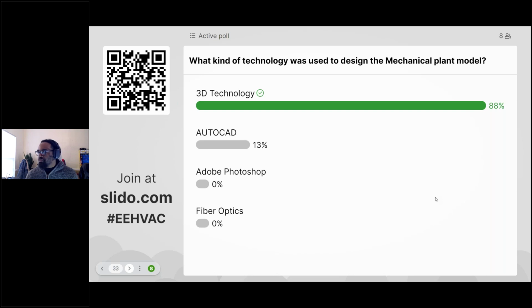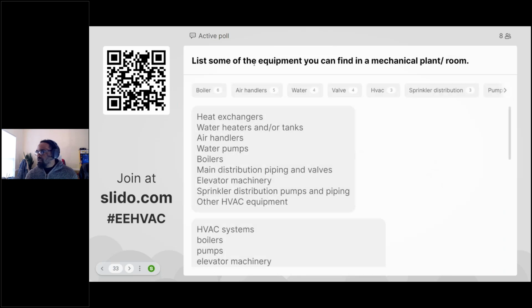Do we have any architects in attendance today? That would be nice to know. List some of the equipment you can find in a mechanical plant or room. And we've got a lot here. We've got boilers, air handlers, sprinkler distribution, HVAC, heat exchangers, water heaters, and/or tanks. Very important to note tanks, for several different reasons, when talking about your hydronic systems, specifically chillers, your air handlers, your water pumps, your boilers, main distribution piping and valves, very important parts of your distribution system. This is where a lot of your issues are going to be present.